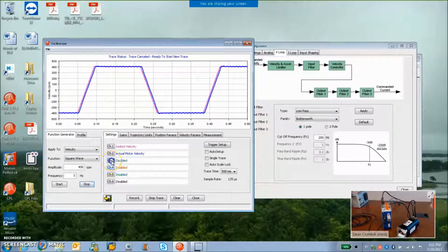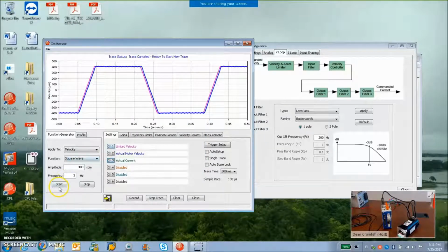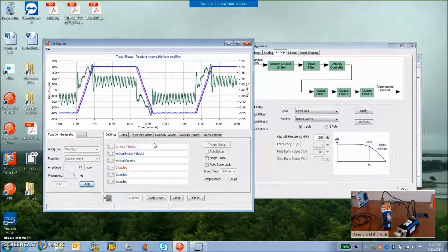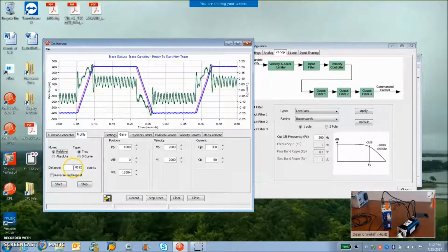Another thing we can look at while we're tuning the velocity loop is the amount of current that we use. So if we're voltage limited or current limited because of voltage limits or current limits, we'll see the limits. That's a little high integral, but we're only using a small amount of current for this, so that's fine. With the load, the story may be different.